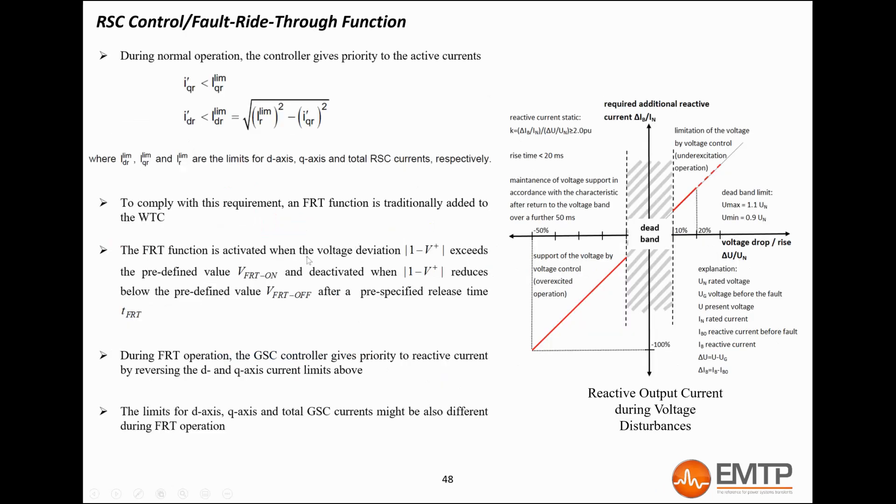Let's now explain the limiter device of the rotor-side converter. During normal operations, the controller gives the priority to the active current. The wind turbines are equipped with an FRT function to fulfill the grid code requirements regarding voltage support. The FRT function is activated when the voltage deviation is above a user-defined threshold, and is deactivated when the deviation goes back below another threshold. When the FRT function is active for LVRT or HVRT, the rotor-side controller gives the priority to the reactive current.